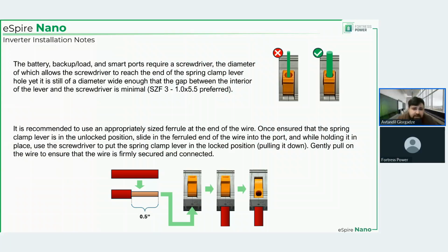Also, when you're putting in the cable, half an inch of the sleeve or jacket or insulation of the cable must be removed, and you slide that in from the bottom, hold it in place, close the spring clamp, and give a gentle pull onto the cable to make sure that it's in place and it's not going to fall out. Obviously, all the way up is the open position for the spring clamp, and all the way down is the closed position. Now, it doesn't say this on the slide, and it will be difficult to show, but when you stick the screwdriver in, there will be one stage when it unlocks and this spring clamp can move freely, but that is not when the cable is allowed to move. You need to push it all the way back so it locks into the unlock position, so to speak, and that's when you can easily slide out the cable.